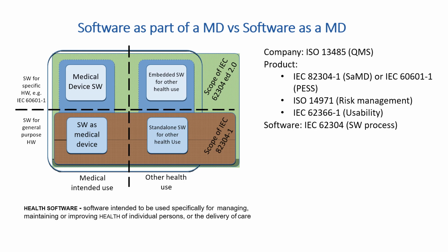Now, depending on your product, you're going to have to follow slightly different standards. In terms of risk management, so how do you manage your risk? How do you assess risk? That's always the same. And once again, it's ISO 14971, and that's your risk management. And then for usability, the standard is IEC 62366-1. So that is just your usability.